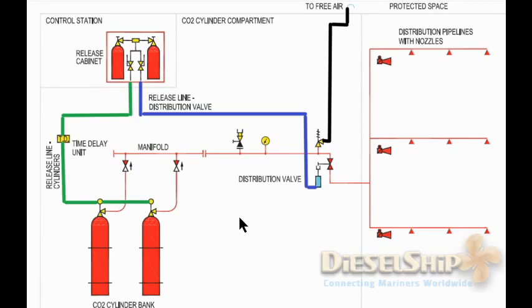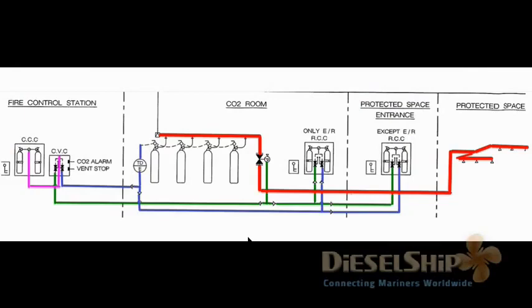That covers the simple schematic system. Now let's concentrate on the actual system present on board a ship. This is one such actual system from a ship I served on. We consider the protected space as the engine room. At the protected space entrance we have the valve control station. Conventionally you also have one in the CO2 room and one at the fire control station, so from three places you can flood CO2 inside the engine room.